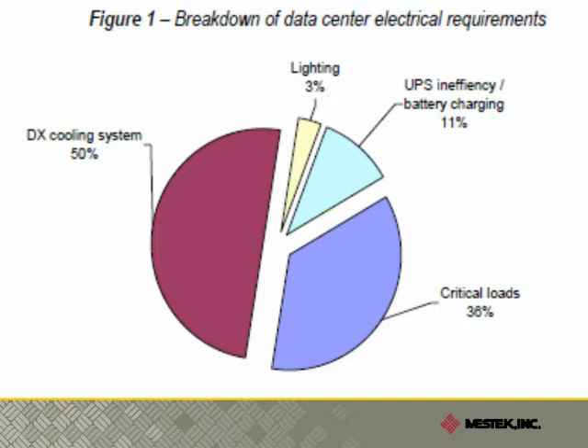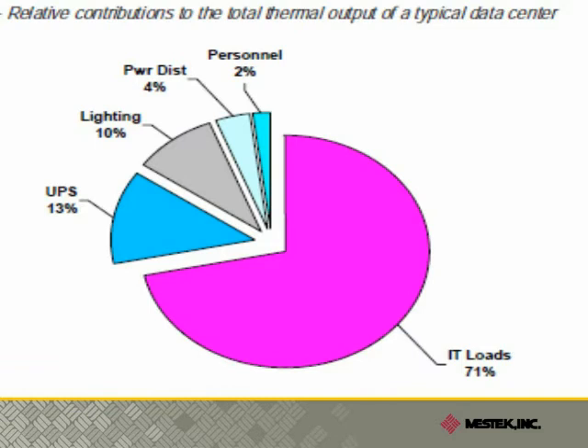Not all of the power that goes into a data center is actually used by the servers. On average, only about 36% of the electrical energy is consumed by the computer equipment. The rest goes into things like backup power supplies, the lights in the building, and the biggest part goes into the building cooling system. All of the energy that goes into a server for processing information ends up being converted to sensible heat. So even though the servers represent only 36% of the energy consumed, they represent over 70% of the heat generated in a data center building.